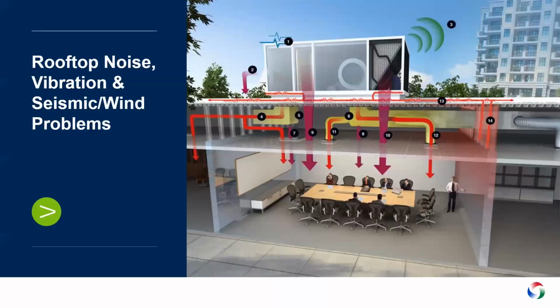For those specific cases, when we have a rooftop unit right above occupied space, like a conference room, office room, classroom, or hospital application, we have identified 14 different noise paths through which noise can travel from the equipment into the occupied space.